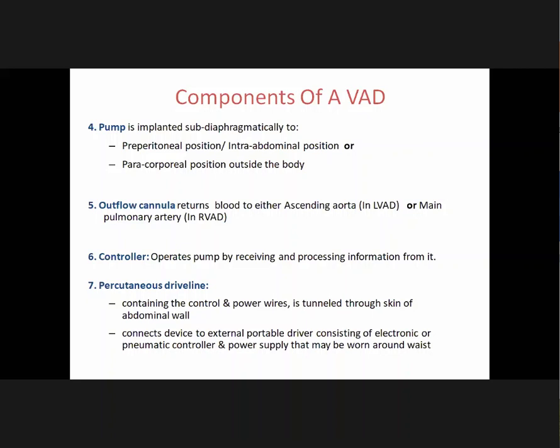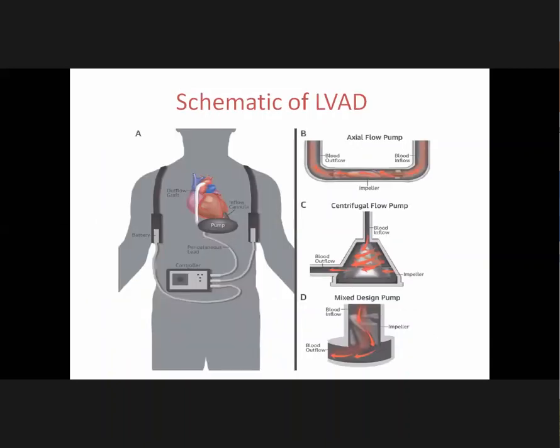The outflow cannula returns blood to the ascending aorta in an LVAD or to the main pulmonary artery in an RVAD. A controller operates the pump by receiving and processing information. A percutaneous driveline containing control and power wires is tunneled through the abdominal skin and connects the device to an external portable driver with electronic or pneumatic control and power supply worn around the waist. The controller manages all variables of the LVAD, powered by two batteries worn on either side.